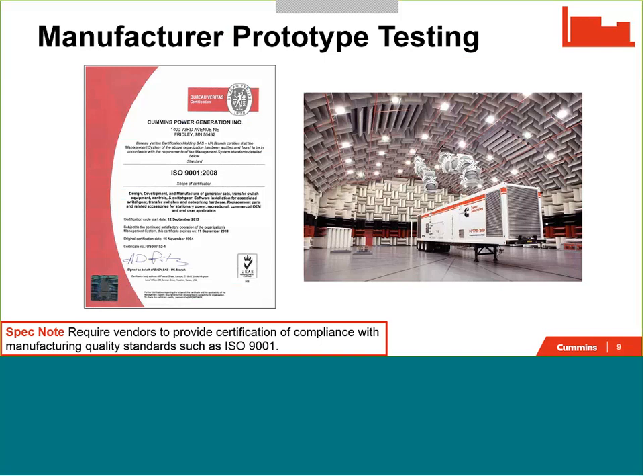The other thing I'll note here, and this goes along very closely with the comment I made earlier, is that I stated that each manufacturer is able to decide what is required for their particular testing procedures for their particular product. Not all manufacturers are the same, and there's a couple things you can look at here as an example. One, on this left-hand side, what you're looking at is a compliance document, a certificate of compliance with a quality standard. In particular, this is ISO 9001, which mandates quality standards or level quality practices of a manufacturer. This is something I always recommend that you require from generator set vendors to supply with their submittal. Every generator set manufacturer in North America should be able to provide you with this document certifying their compliance with this particular quality standard.